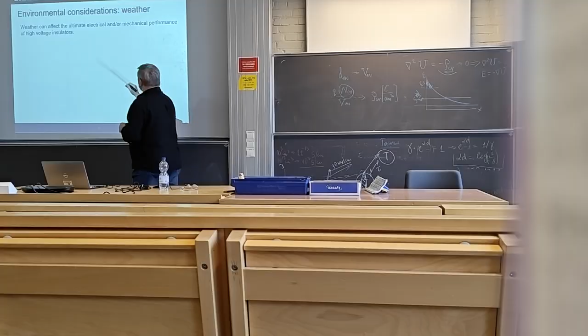Insulator. And what? Okay, nothing will happen. It's a salt. It's just sitting on the crystals, sitting on the surface. The insulator string always has some safety margin. Not much will happen. If one nice morning fog comes, or light rain, or something like that, that's a disaster. Because then you have moisture absorbed by this layer, and it creates a kind of solution, like an emulsion, which is conductive. And then you have huge leakage current flowing through the creepage distance, actually creating more or less a semi-conducting material which just short circuits the insulator. So this is the problem.